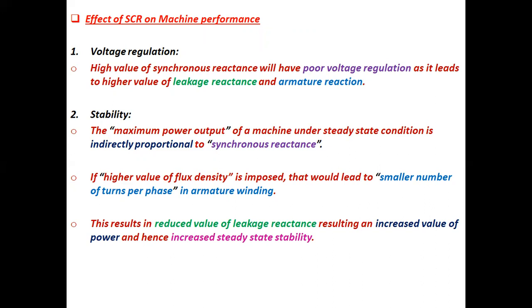Very important: the maximum power output of a machine under steady state condition is inversely proportional to synchronous reactance. If a higher value of flux density is imposed, that would lead to a smaller number of turns per phase in the armature winding. This results in a reduced value of leakage reactance, resulting in an increased value of power and hence increased steady state stability of the machine.